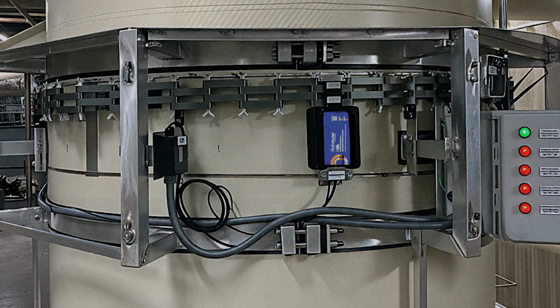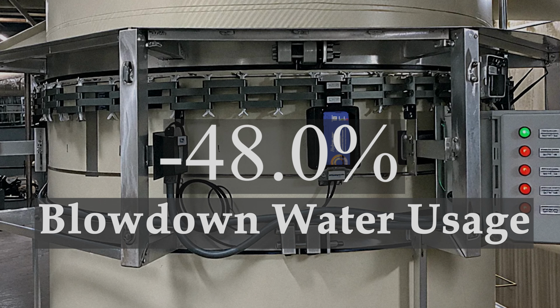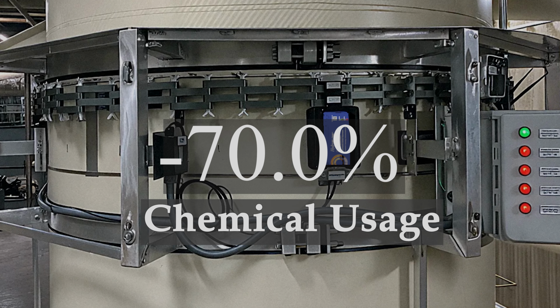HydroFLOW helped the power plant achieve a 48% blowdown water reduction, which equals roughly 60 million gallons per year, while chemicals were reduced by over 70%. No indication of scale or biofilm in the condenser or cooling tower during inspections.